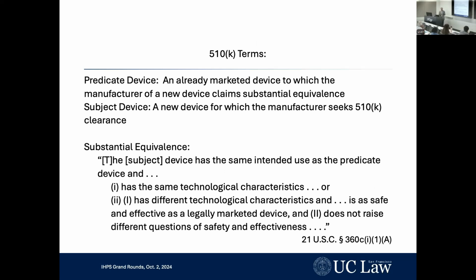First, it has to have the same intended uses. Second, it either has to have the same technological features, or if it has different technological features, it has to be as safe and as effective. And notice it's not more safe and effective, it's as safe and as effective, right? So it's a non-inferiority standard here, all right? And it doesn't raise new concerns about safety and effectiveness. But the bottom line is it just has to convince the FDA that its new device is close enough to a device already on the market that we don't have new concerns about safety and effectiveness.